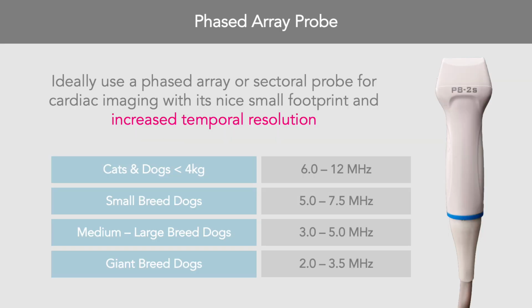For cardiac scanning, it's recommended to utilise a cardiac, sectoral or phased array probe, all names for the same thing. The footprint of this probe is nice and small and should easily fit in the intercostal spaces. Helpfully, this transducer confers an increased temporal resolution. So temporal resolution represents the ability of an ultrasound system to distinguish between rapidly moving structures from one frame to the next, such as the movement of the heart in the cardiac cycle. Microconvex probes typically do not have high enough frame rate, and thus the image may blur a little bit.